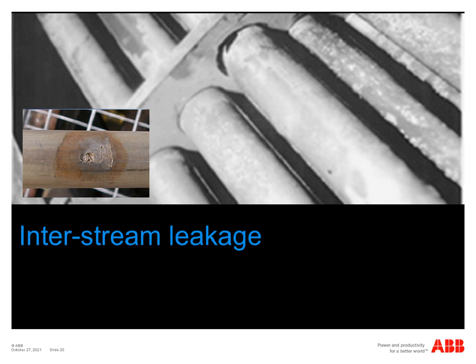Overpressure of the cooling system. Gas release from the cooling system. So the gas has come through from the high pressure side to the low pressure side, and now you've got gas release via somewhere on the cooling system, such as from a cooling tower, say. The tubes might just leak a bit, or they can suddenly fail across the tube diameter. So from fretting damage on a baffle, say, you could credibly suddenly have a full failure of a tube in the exchanger. However, you wouldn't consider it credible most of the time to have a failure across multiple tubes. So normally your worst case situation is a complete failure of one tube.